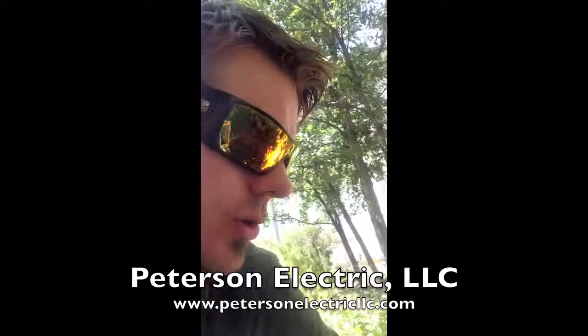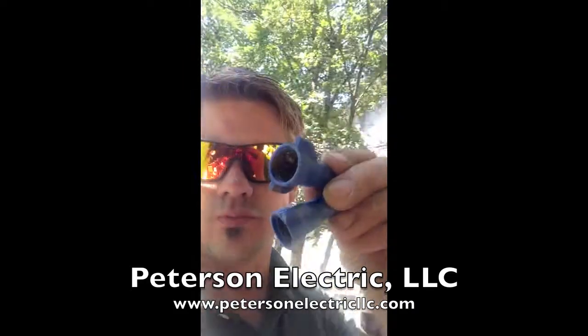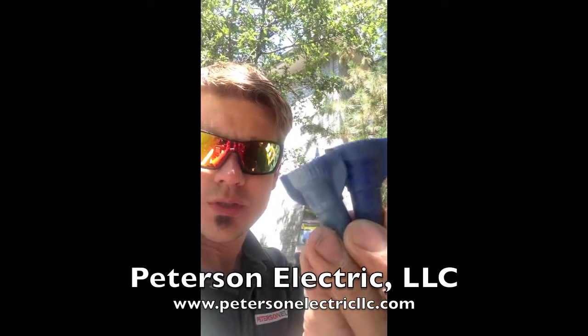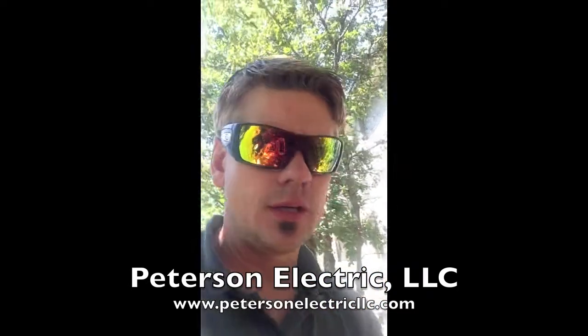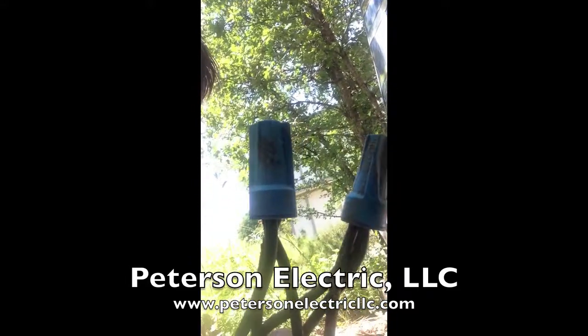So right here I can show you really a poor connection. Somebody used some typical blue wire caps that you get at Home Depot, and they're not even rated for outdoor use. These are something you'd use in commercial with some 10 gauge wire. Another connection a guy made right here, if you can see this, nothing's taped up. That's a poor connection as well, so water's getting in there.